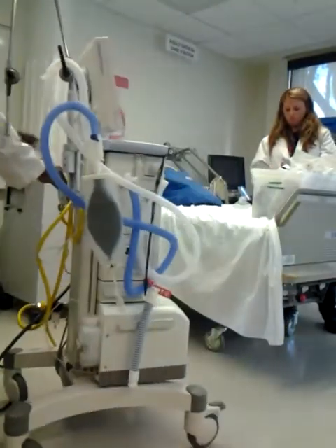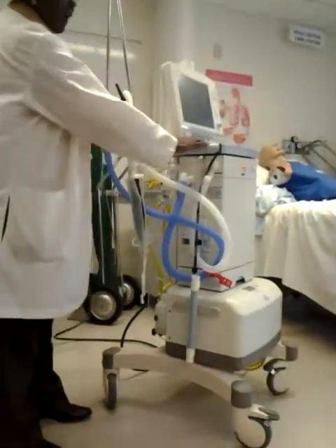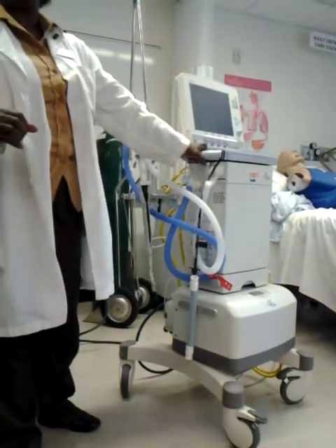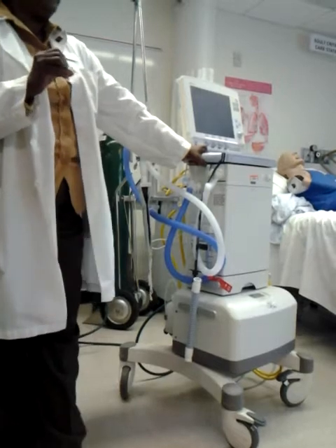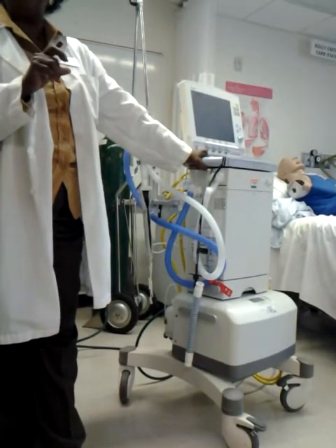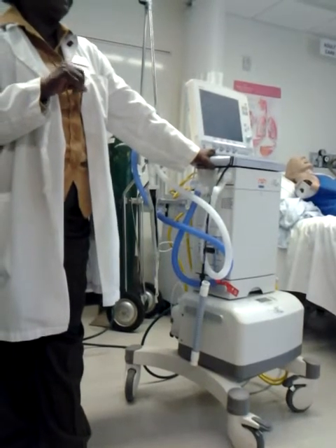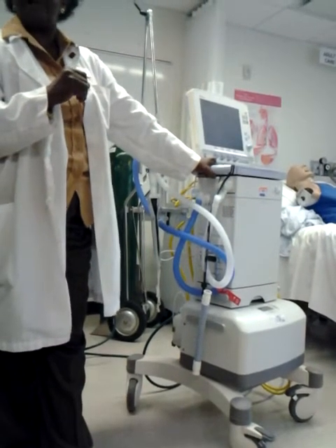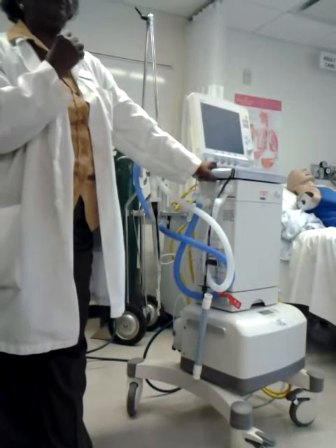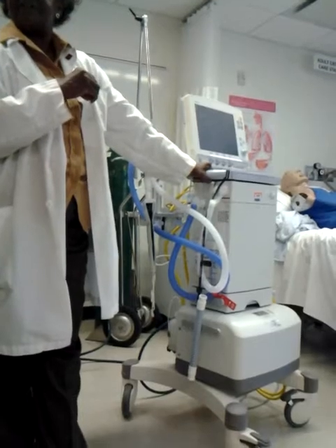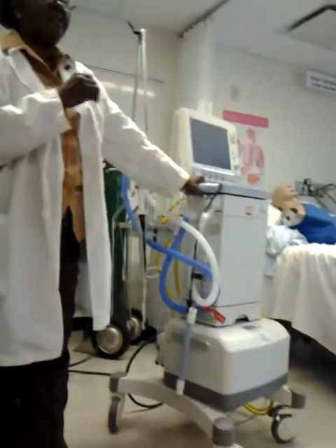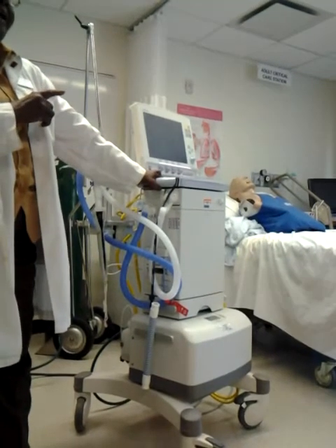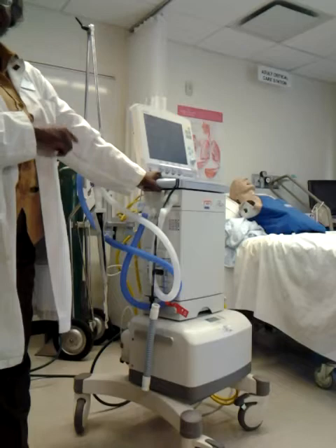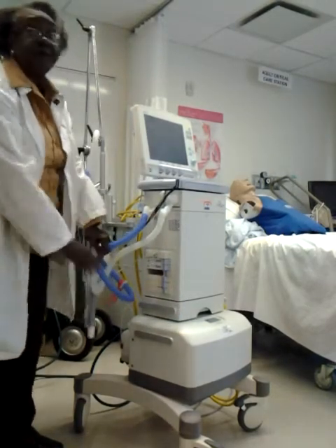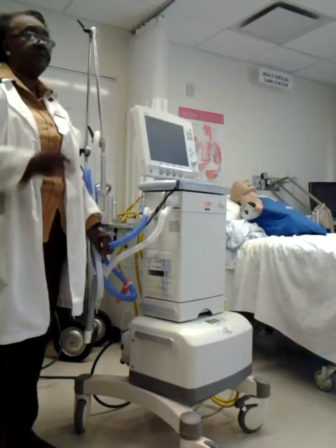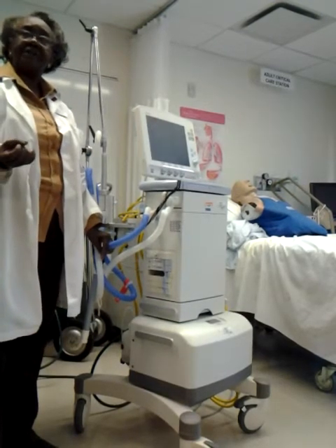The other thing that you need to be aware of with this device is you do have backup batteries. If your electricity runs out, or if you're in the hospital, you probably already know they have specific plugs in the wall that you need to plug things like ventilators into, and they're usually marked with red or a red dot. That's so the ventilator is hooked into the hospital's backup generator. So if electricity goes out, it usually takes a couple of seconds and it immediately clicks over to the generator. But this one has backup batteries. So if you're transporting a patient, and I've had to transport infants from Monmouth Medical Center to another institution using this device.